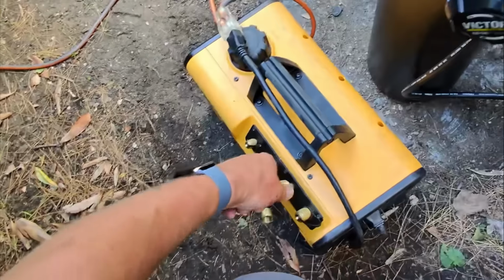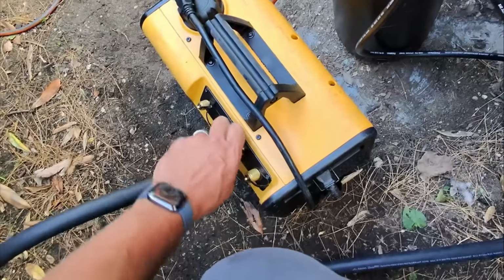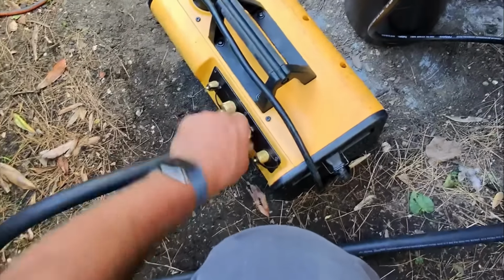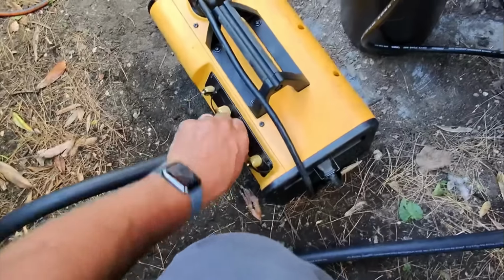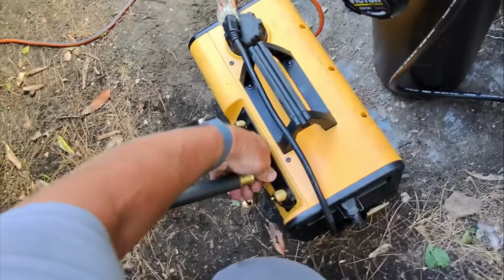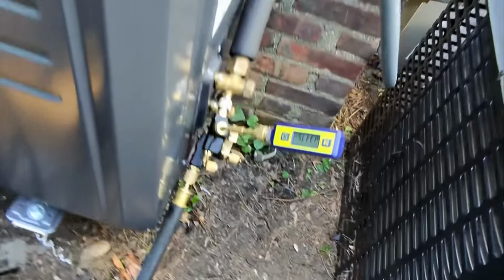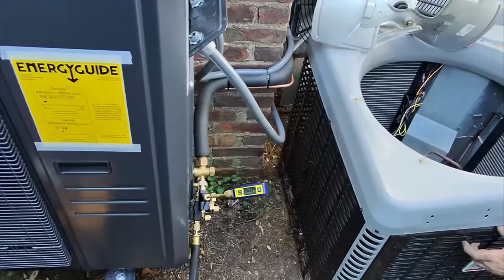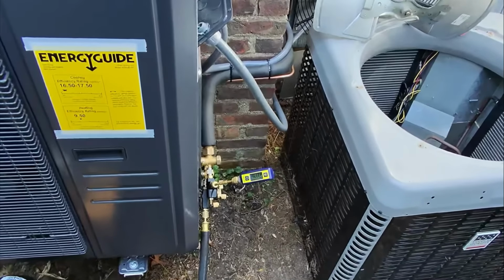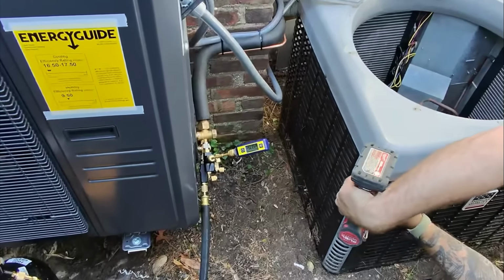All right, we are now hooking up our vacuum hoses to the vacuum pump from our Schrader core removal tool. For the micron gauge, I'm using the Blue Vac Plus micron gauge.